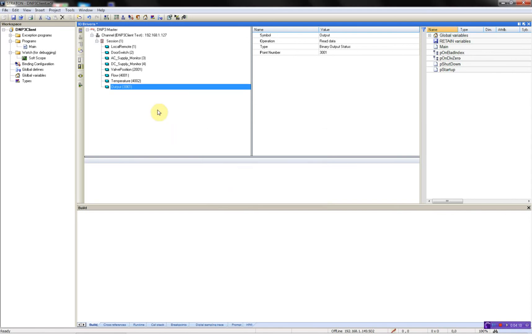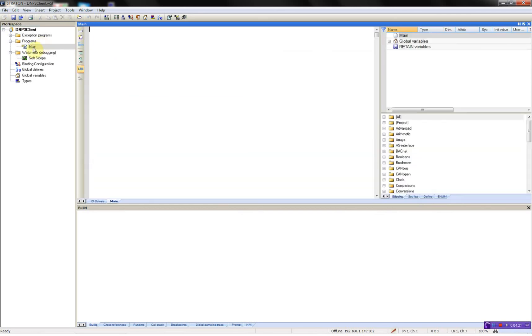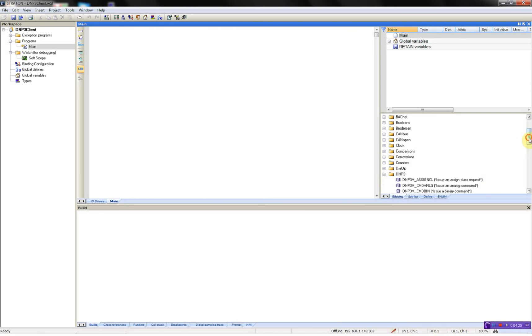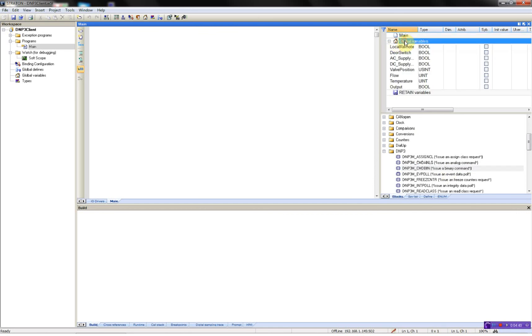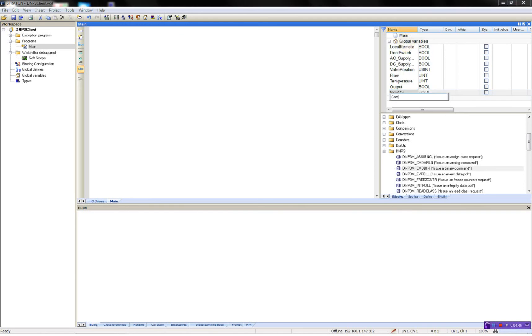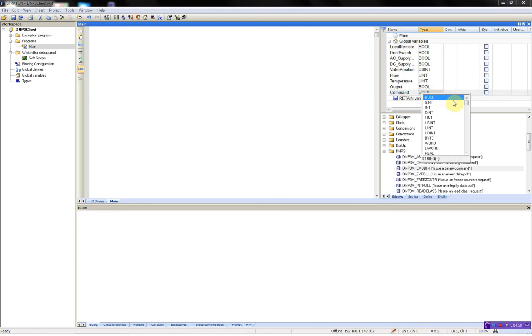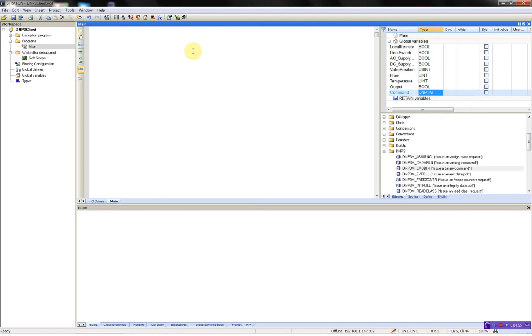Now I've put in all my data points, then I'll just add the code for sending a command to the server. This is done by opening the main program, then expand the block DNP3 master. Here we have a command called DNP3M underscore command bin, issue a binary command. I'll just add a variable called command and it is of the type DNP3 command bin. Now I can write command and I will have a variable called activate which is actually activating this command block.